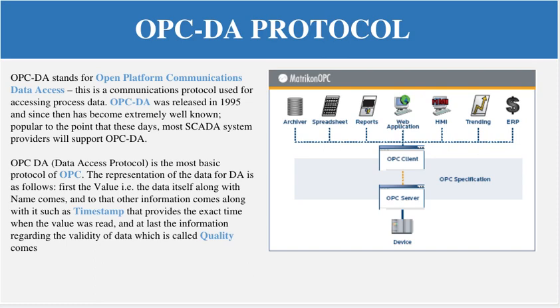The representation of data in OPC DA includes first the value — the data itself along with its name — and along with it comes other information such as a timestamp, which provides the exact time when the value was read. The last piece of information is regarding the validity of the data, which is called quality. So OPC DA is used to transfer data from source to destination, and a good example is manufacturing companies where data is transferred from the plant to the IT department using the OPC DA protocol.